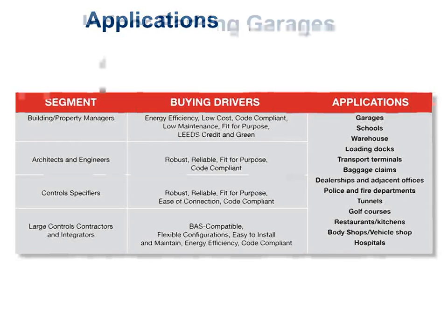Right, so I'm going to go through one slide here on each of the major applications that you'd have for commercial grade gas detection. First one being indoor parking garages, which you mentioned a couple times already. You definitely want to measure carbon monoxide. That's the vehicles that you're going to be measuring. You may also want to measure nitrogen dioxide if you're going to expect a lot of diesel vehicles. A normal parking garage does not have a lot of diesel vehicles, so typically you don't need to measure that.